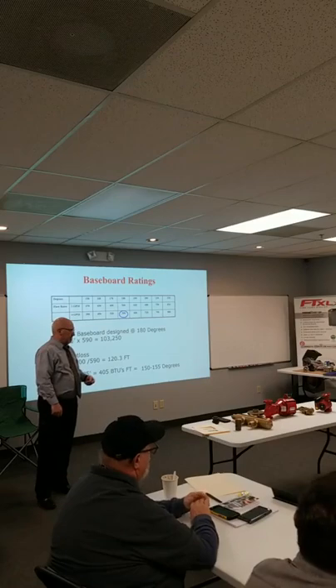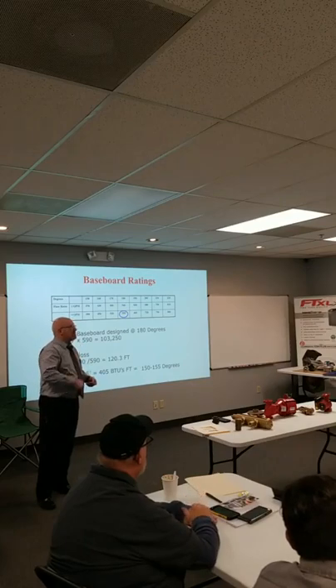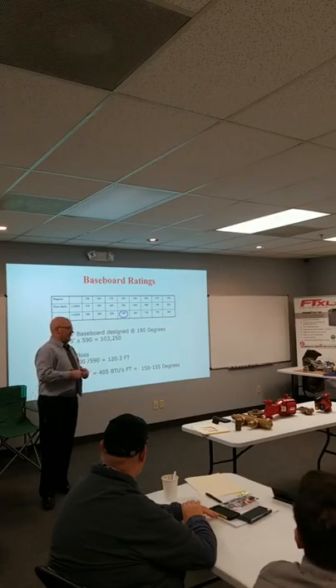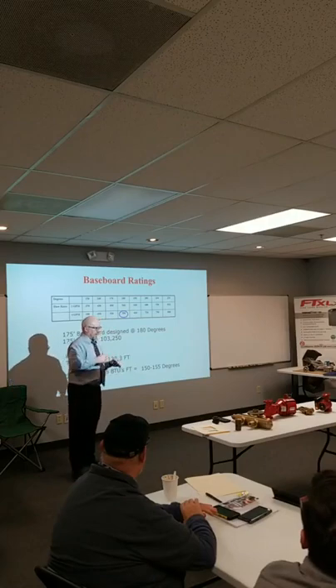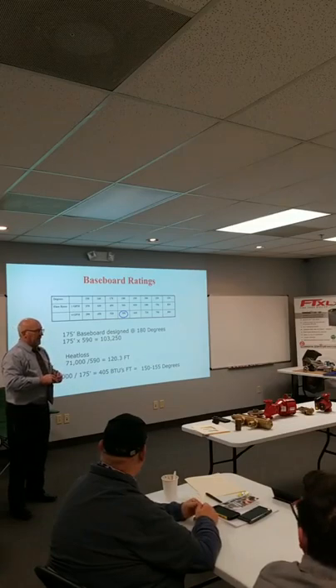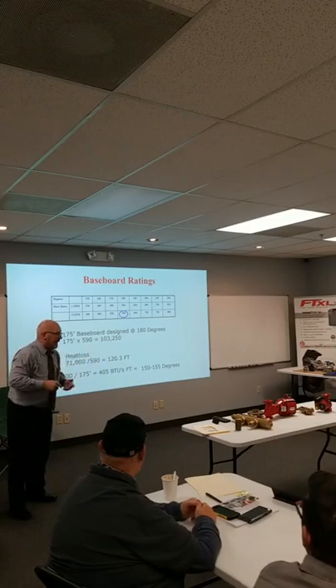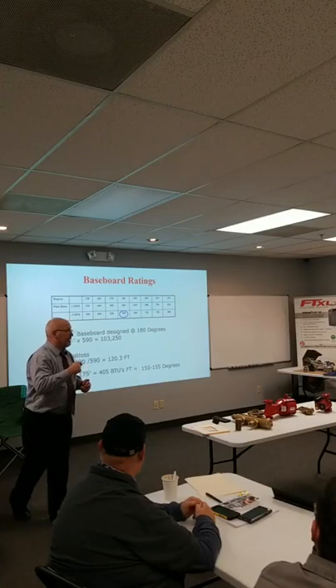The weather data can say 0 or 1%, 2.5%, or 5%. So at 5%, 95% of the time it's warmer than this. When we do radiant, we do snow melt. We do a lot of snow melt sizing based on a percentage like that. 100% snow melt all the time, and then we have ratings done like that. But typically, most people aren't going to do all that math. They're just going to pick a number, whether it's 0 or 10 or 20, and do their heat loss.